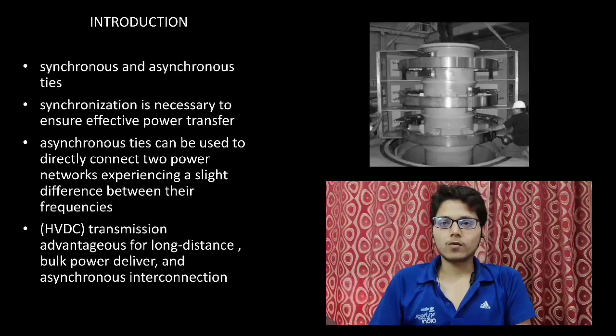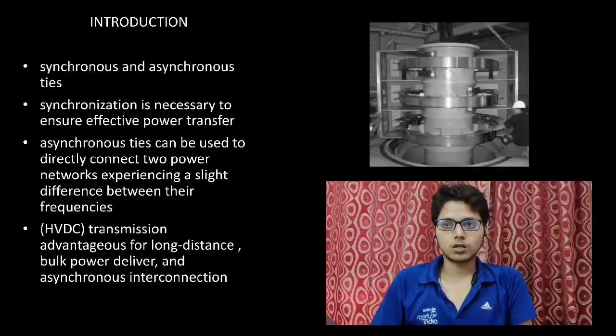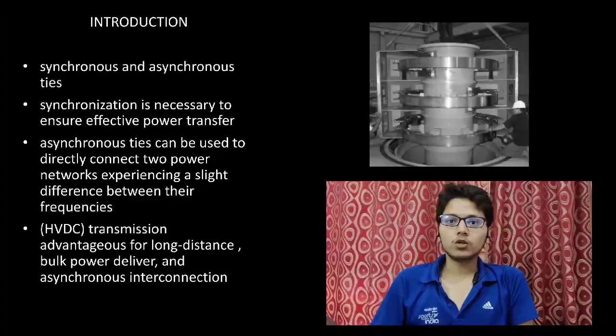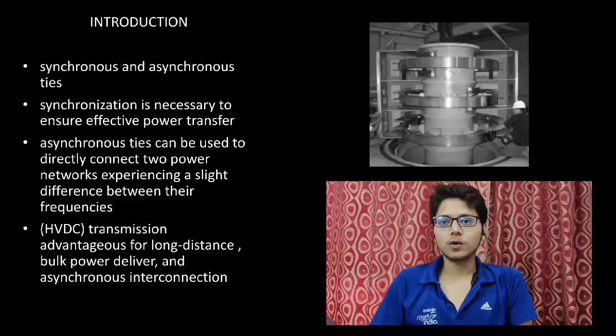Interconnection between power networks can be classified into synchronous and asynchronous ties. Synchronous ties are the most common type in practical power systems. However, synchronization between involved networks is necessary to ensure effective power transfer between them, which is a challenging task, especially with weak networks. On the other hand, asynchronous ties can be used to directly connect two power networks experiencing a slight difference between their frequencies.